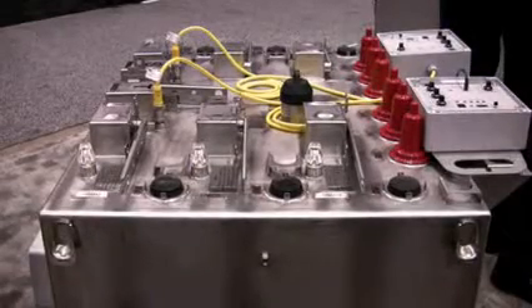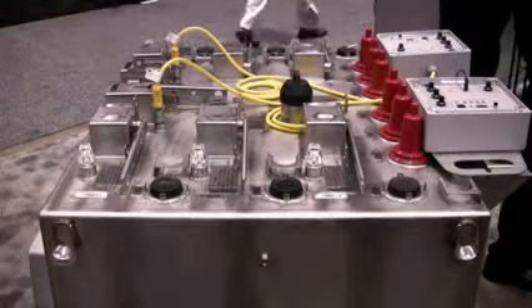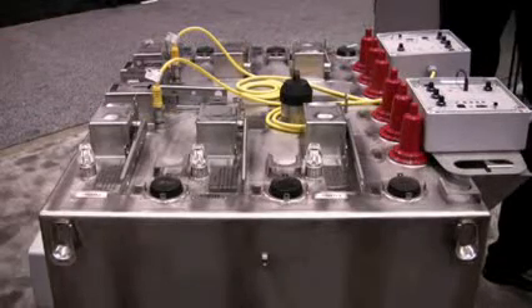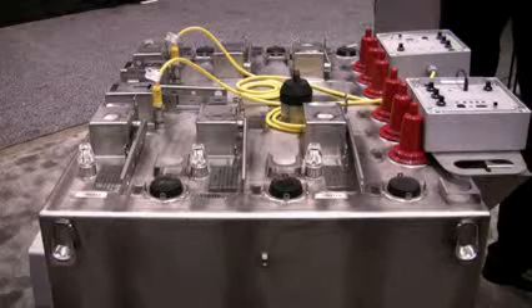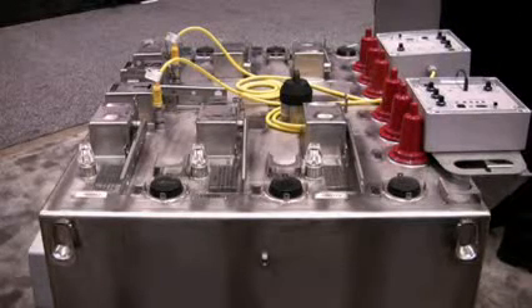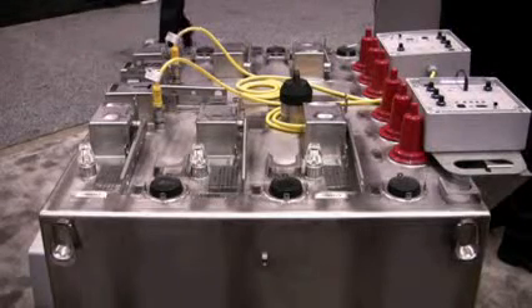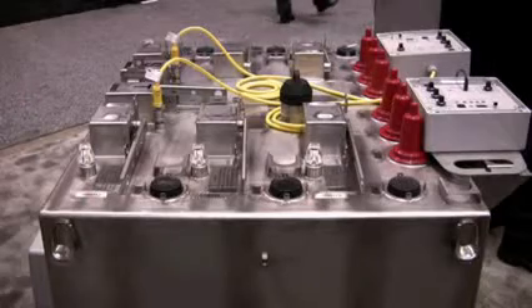This is a four-way submersible unit. As you can see, it's stainless steel, 304 type. It has two three-phase switches, and it has two ways of single-phase vacuum fault interrupters that can be tripped either three-phase or single-phase, and they can be reset either single-phase or three-phase.